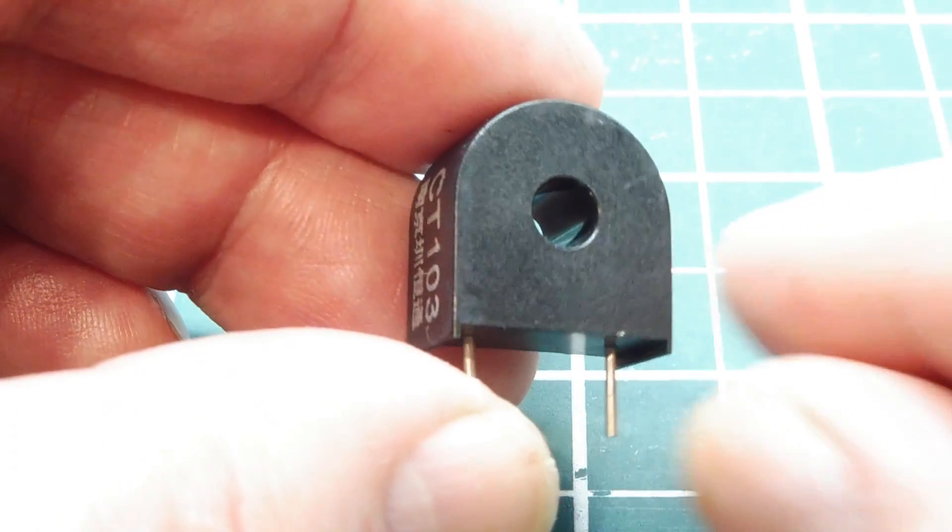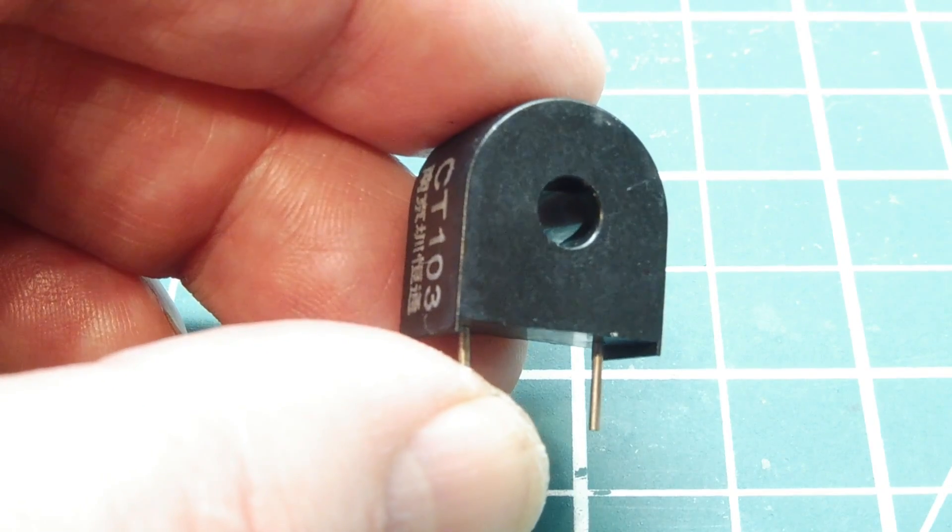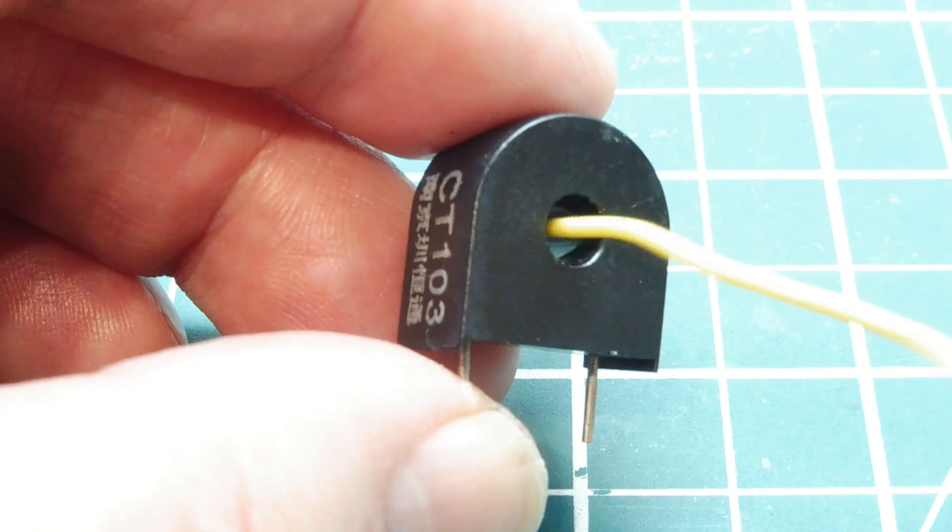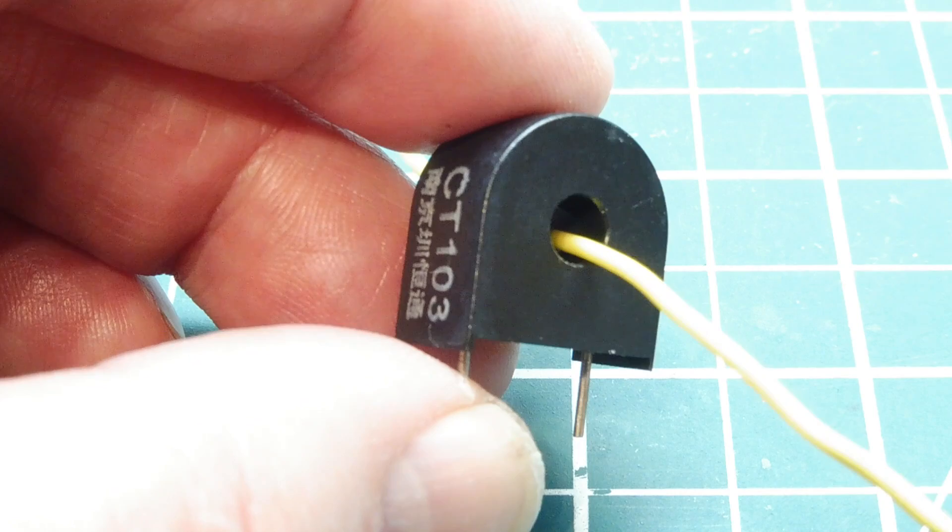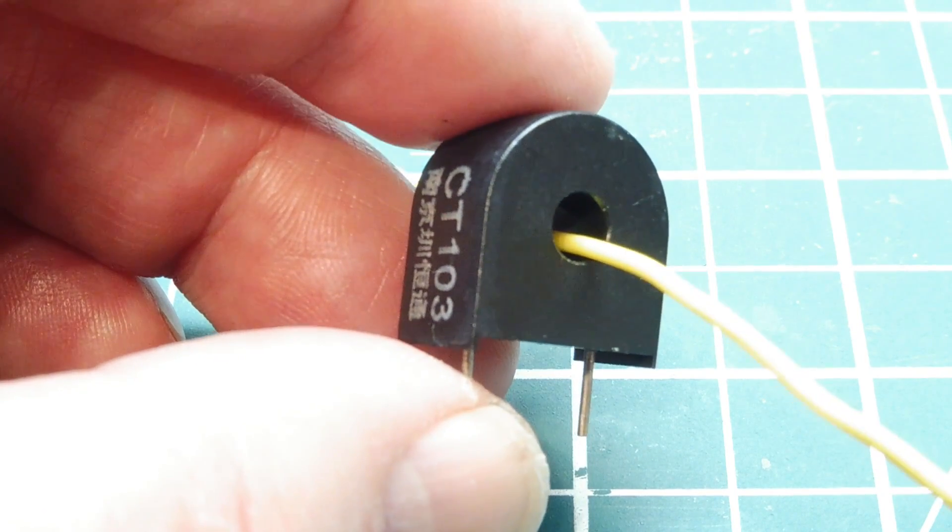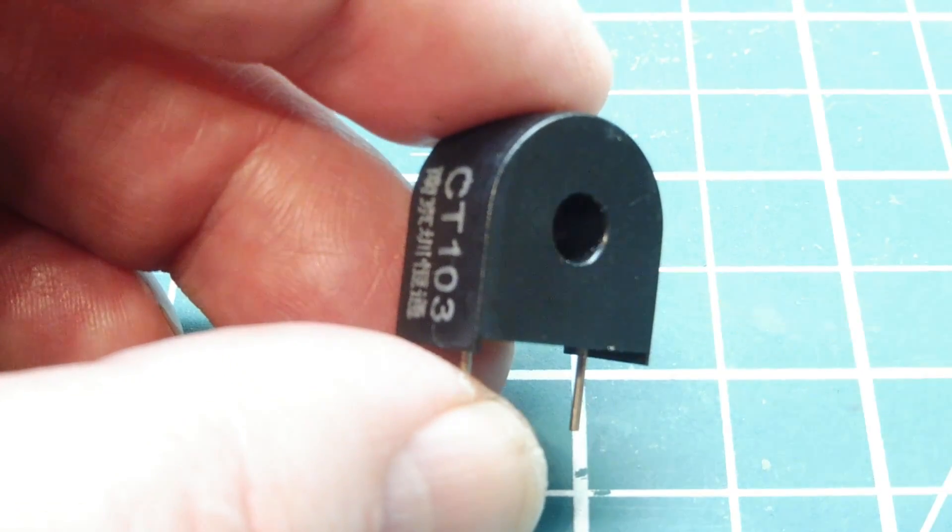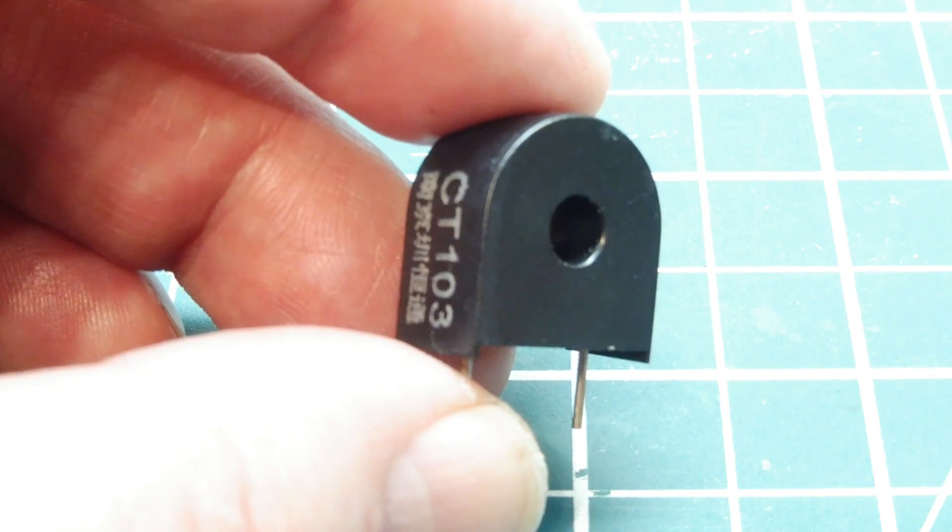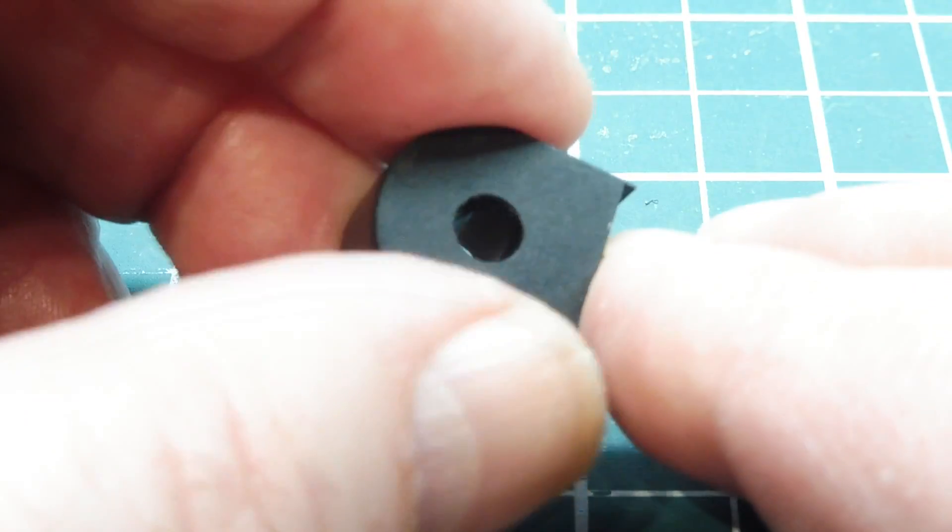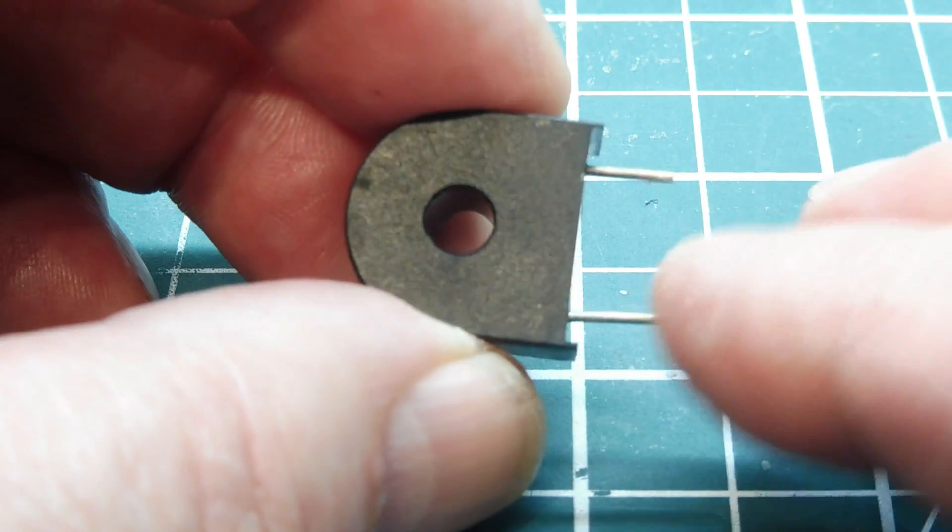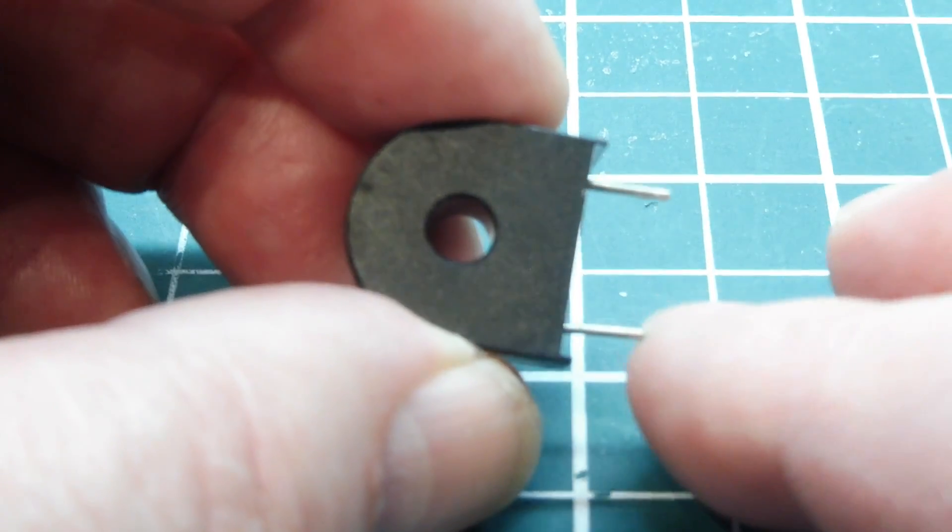Now the primary winding of this transformer is a wire that goes to the center of the toroid. Now if we put a current through this wire at five amps we'll get five milliamps flowing at the output of the sensor. Now this is a step up transformer, it's a thousand to one step up transformer, so there'll be a high voltage at output so we can't leave this open circuit, we have to shunt it with a resistor. That resistor is called a burden resistor.